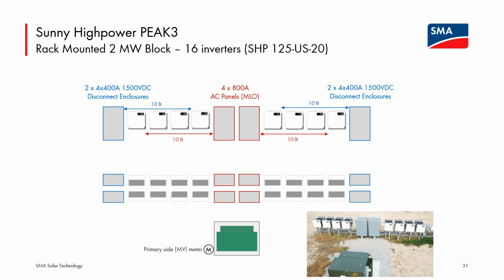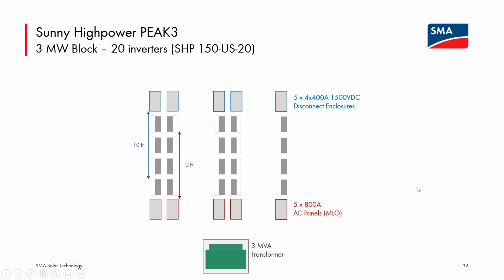Waiting to the evening and having 2 folks swap out an inverter is a very straightforward way to bring one inverter back online, rather than necessarily diagnosing everything and getting a service tech to show up if that's required and rectify the situation. So I think, again, all of these are factors driving adoption of the PEAK3 to higher and higher plant size. And I think it's even exceeded SMA's expectation for this type of plant design.